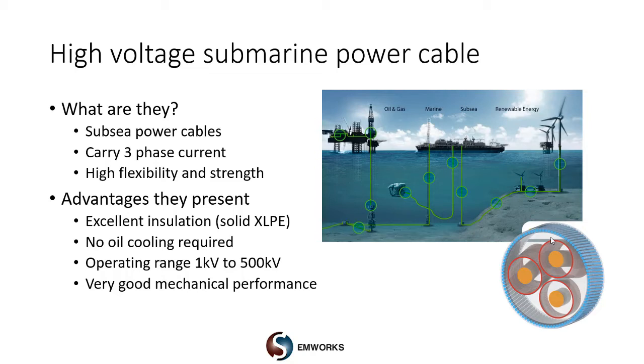Let us take a look at some of the advantages they present. They have excellent electrical insulation — the solid XLPE, which is really the core of the submarine power cable, provides this. They don't need any oil to achieve their cooling. They have a wide range of operating conditions all the way from 1 kV to 500 kV. And because of their structure, they have very good mechanical performance.